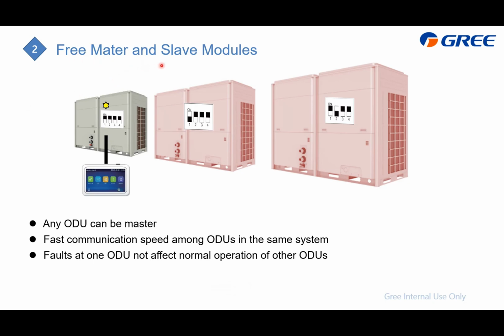Free master and slave modular. That means in a modular system, if you need to set the master outdoor unit, just change this switch and then connect this controller to it. Also in this example, there are 3 heat pumps here, and the only difference between these 3 is the switch on the PCB. If this wired controller connects to the heat pump, we require the switch setting like this.